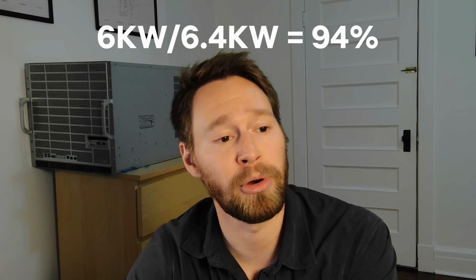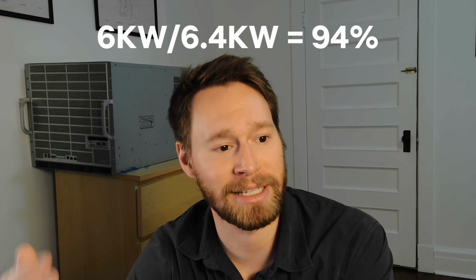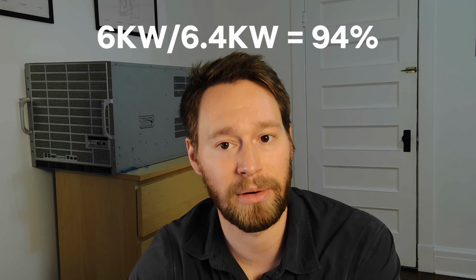The math changed with 5090s because they ended up needing just under 6 kilowatts for the full 8X server. The CPUs take more power, the RAM takes more power, the GPUs take more power - everything was scaled up. With 6.4 kilowatts of capacity and almost 6 kilowatts of IT load, eventually something would fail and the redundancy was very bad. If we lost a PSU, we'd be well below the required power needed at a moment's notice. So we ended up going with 5 PSUs in each of the 5090 servers.